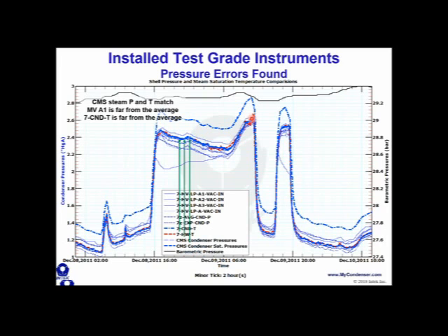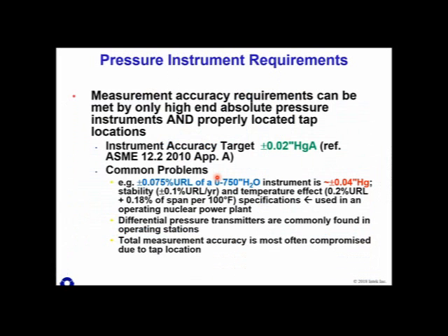So my point here is that we've got 3 very good quality transmitters. Unfortunately, they were installed without basket tips, with static taps near high temperature drains. At least that is the supposition of why these values were so wide ranging and why this one changed so drastically over time. So you can have good gauges without being installed properly.